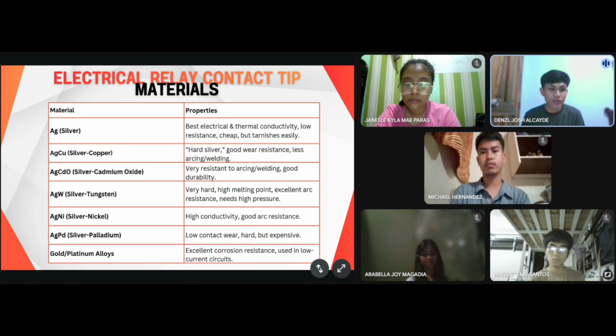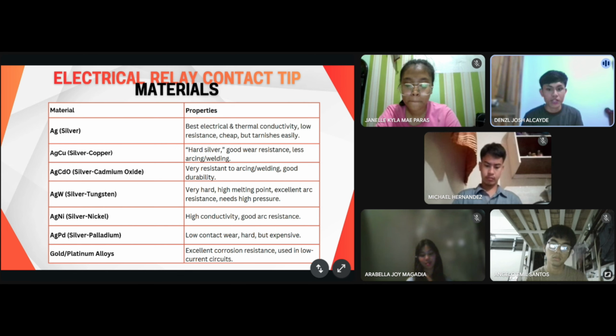Now let's proceed with the electrical relay contact tip, which is all about the materials and its properties. So as shown in the table presented in the slide, different contact materials are chosen para tumagal ang relay depending on the load. For example, silver or AG gives excellent conductivity pero madaling mag-tarnish, or meaning to say, madaling umitim or mag-darken kapag exposed sa air. However, harder materials like silver-tungsten are used for high current circuits because mas mataas ang kanilang melting point and arc resistance. Meanwhile, gold or platinum alloys are used for tiny electronic signals to prevent corrosion.